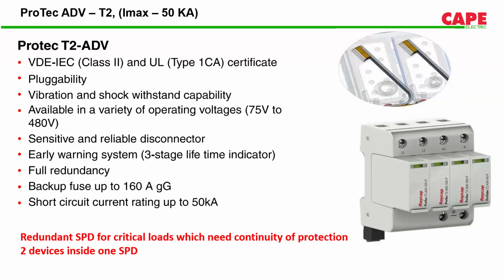The advantage of these particular SPDs is, once the primary device fails, you see an indication given in this SPD, which is green in color. Once the primary device fails, this green color will change to yellow, and then you can keep a spare with you. Once the yellow turns to red, immediately you can change the spare. So with this particular SPD, you can get continuity of supply as well as continuity of protection.